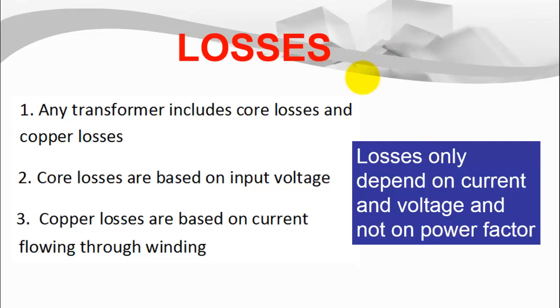I hope you clearly understand why transformers are rated in VA or kVA and not in kilowatts or kVAR, because once again the transformer is a source and the source must be expressed in kVA, whereas the loads are expressed in kilowatts and kVARs.